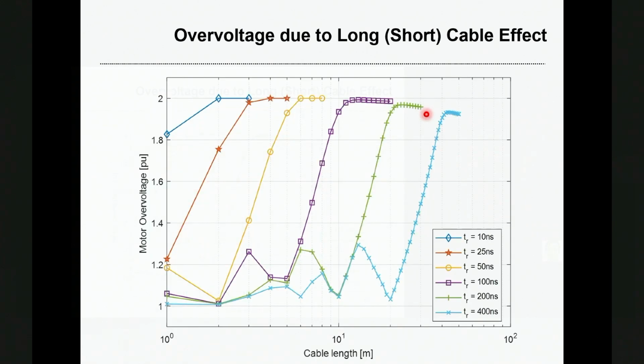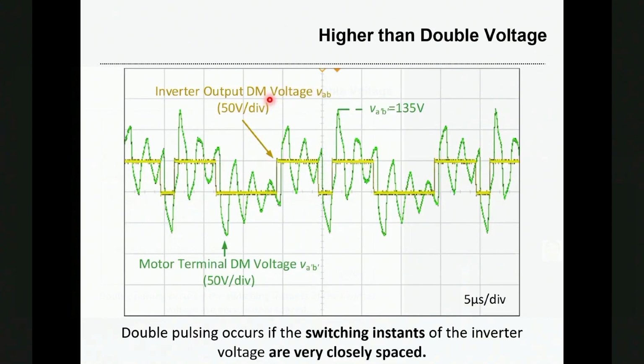This slide shows the motor over voltage with respect to the cable length under various switching speeds. For example, for a rise time of 25 nanoseconds, which is a typical silicon carbide MOSFET switching speed, with about 3 or 4 meters of cable, you will have a double voltage at the motor terminal, which means the motor terminal voltage is twice the inverter output voltage with only 3 or 4 meters of cable length. And the motor terminal over voltage can even be higher than double. In this case, the inverter output voltage is only 50 volts, but the motor terminal voltage has reached 135 volts, even higher than double the inverter output voltage.